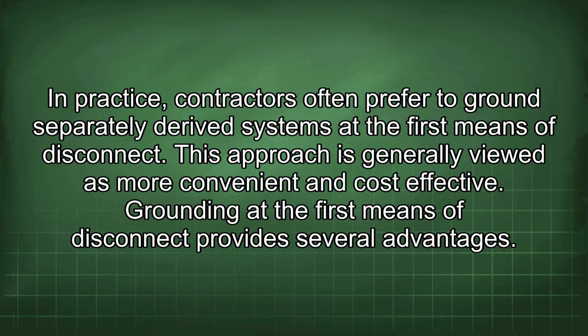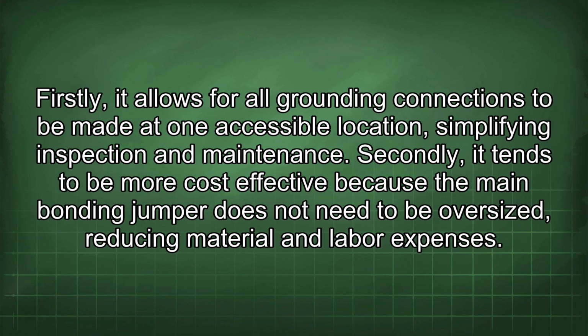In practice, contractors often prefer to ground separately derived systems at the first means of disconnect. This approach is generally viewed as more convenient and cost-effective. Grounding at the first means of disconnect provides several advantages. Firstly, it allows for all grounding connections to be made at one accessible location, simplifying inspection and maintenance.